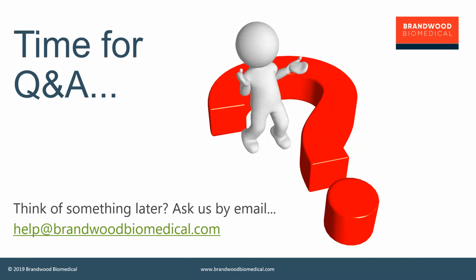Well, actually, no. Really what you have to do is a gap analysis to understand how much has changed between one version of the standard and the next. And very often, when a standard is revised, nothing is taken out and very little is modified, something is added. So often it will be the addition of a new test method which is equally applicable. In the recent revision of the standard for irritation, they added an in vitro irritation test. They didn't take anything else out. So if you had previously done testing using an in vivo method, then that method is still included in the standard and you would still be compliant.